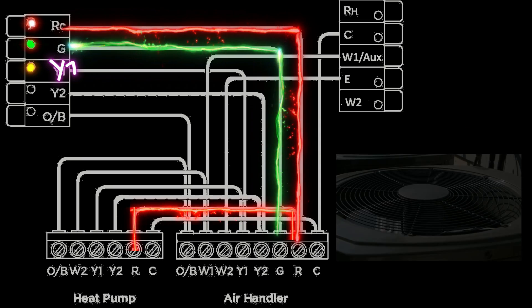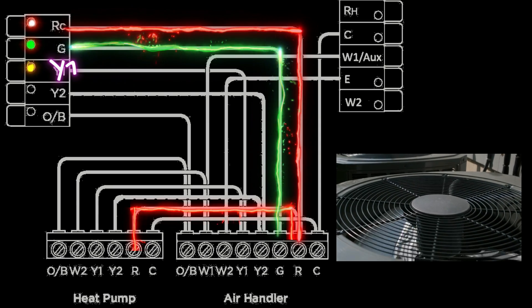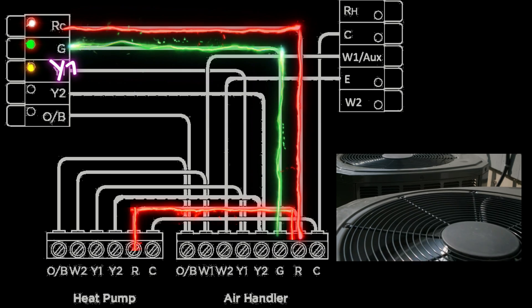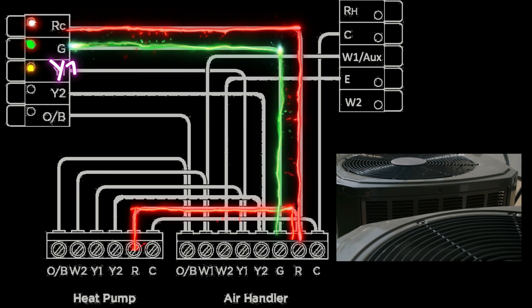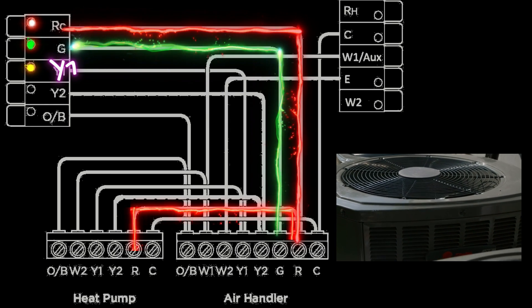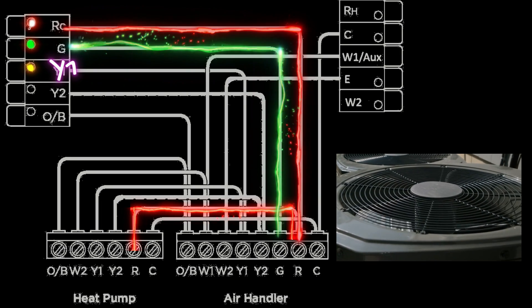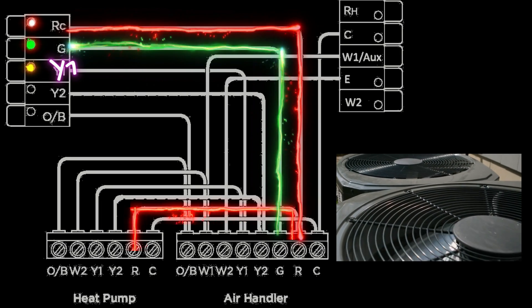It's better to think of the Y terminal as the terminal that turns the outdoor unit on and off. Now the reason why a lot of people think it's for cooling is because in a straight air conditioning system that is the only time you're turning on the outdoor unit, in cooling mode.